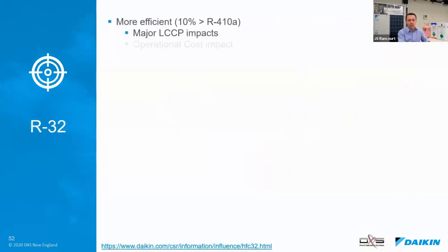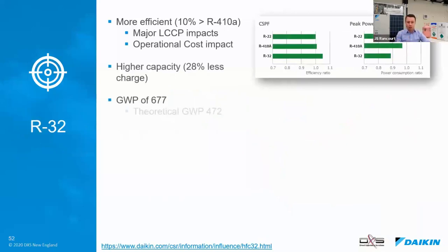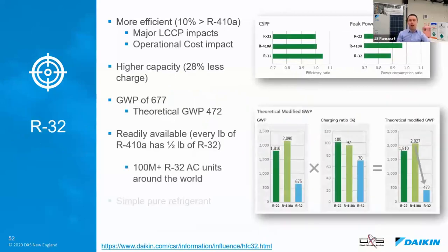If we look into more detail, R32 is more efficient than R410A, by about 10%. It's got a higher capacity, so you need less of it. Its GWP is 677, but if you look at the fact that you need less of it, its theoretical modified GWP is 472, even lower. It's readily available because it's already being used everywhere. Every pound of R410A has half a pound of R32 already in it.